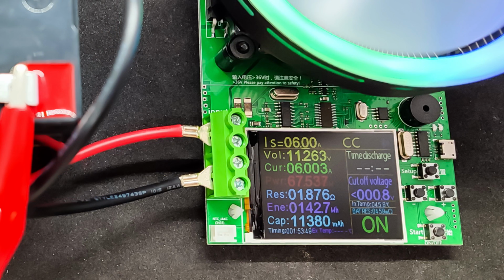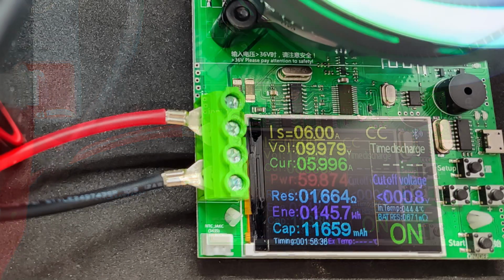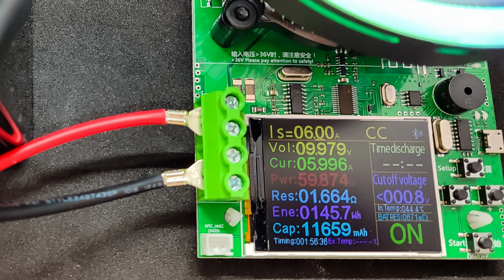1 hour and 53 minutes have passed. Almost 143 watt-hours of energy, or 11.38 amp hours, have been delivered. The voltage dropped to 11.26 volts. According to the instructions, at this point, I was expecting a disconnection from the power through the BMS board. However, the disconnection did not occur, and after 3 minutes when the voltage dropped below 10 volts, I disconnected the load myself.